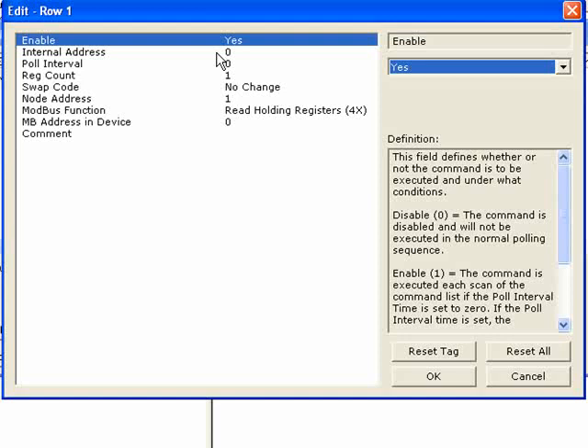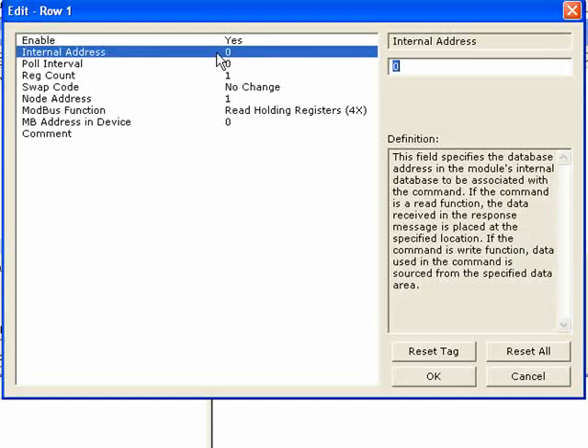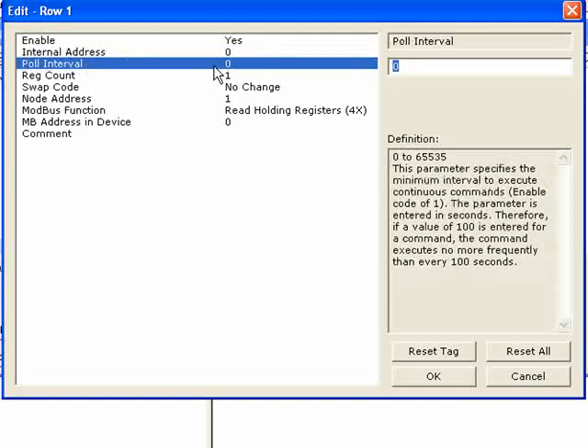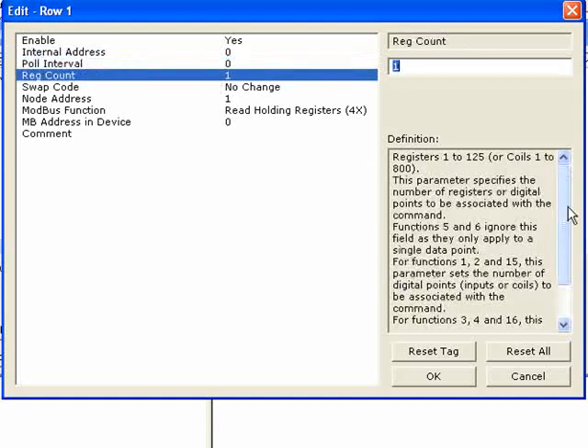You also have a conditional command, which is only valid for write commands — it executes only if values within the database change, which happens when the CPU changes them. The internal database address is the address for the command: for a write command it looks at that database address and sends those values out; for a read command it grabs values from your Modbus devices and stores them at that internal database address. The poll interval defines how often the command will execute. The register count defines how many registers to read or write on the Modbus network.